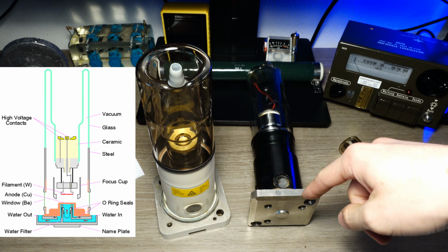Here on the back you can see that 4 screws are used to keep this lower part together, and they simply come out. And then you can just take the tube apart gently, and you can see that it's composed of these two parts. So here you have the target. You can see here it's all made of copper to conduct heat better. And the target is flat, as you can see inside.